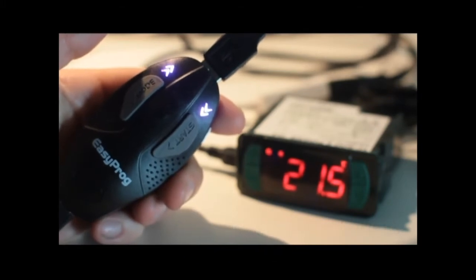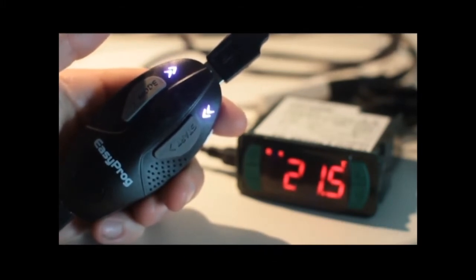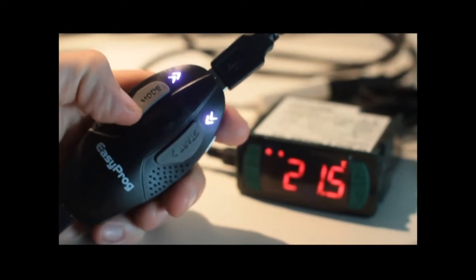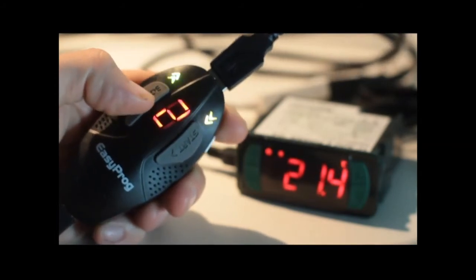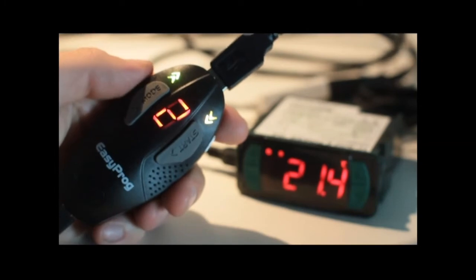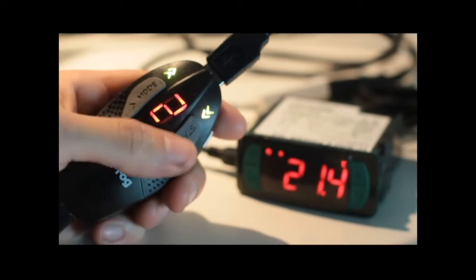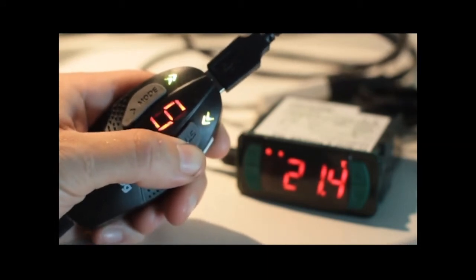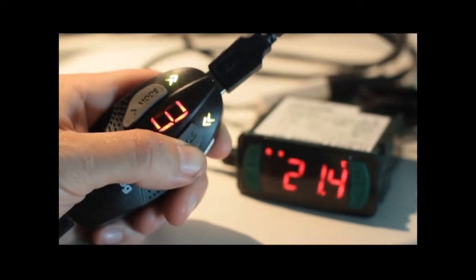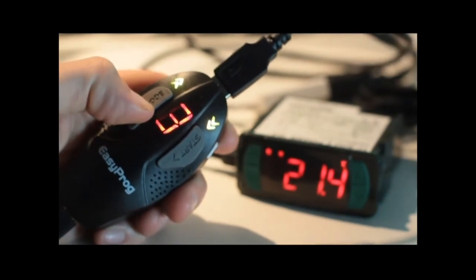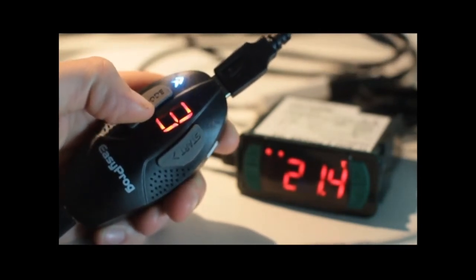It is possible to copy presets from the controller to one of the 9 available spaces in EasyProg. To do so, press the Mode key for 1 second. Observe that the yellow LED lights will switch on. Press the Start button and select the number of the desired preset. After that, press and hold the Mode key for 1 second and then release it to exit the preset selection menu.